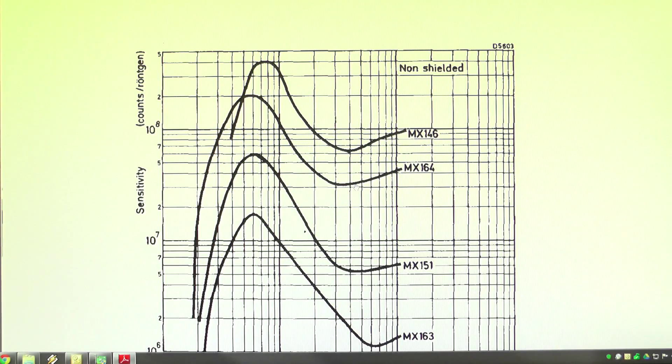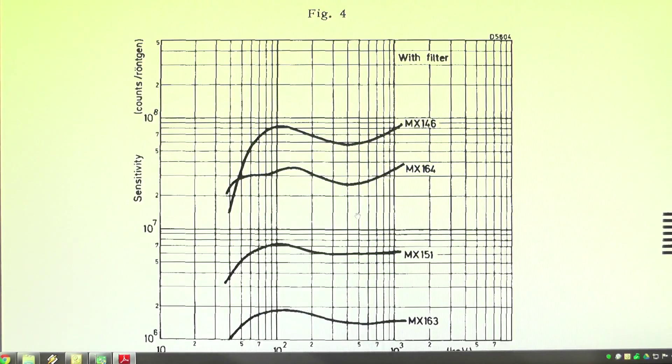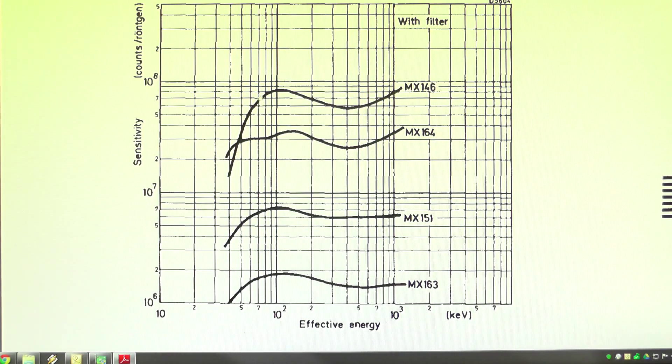Now it's got some example graphs here. We don't actually have the tube I have in this which is the MX145. But we can clearly see that between these four different tubes the profile is pretty similar just at different amplitudes. So this is non-shielded. And then when you have the shielding on you get a much flatter energy response from the tube.